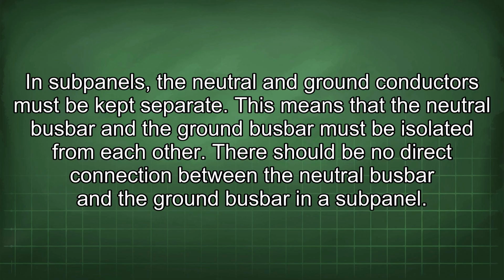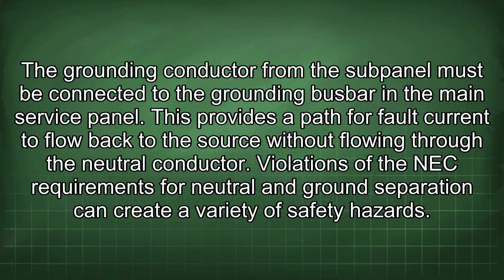In subpanels, the neutral and ground conductors must be kept separate. This means that the neutral busbar and the ground busbar must be isolated from each other. There should be no direct connection between the neutral busbar and the ground busbar in a subpanel. The grounding conductor from the subpanel must be connected to the grounding busbar in the main service panel. This provides a path for fault current to flow back to the source without flowing through the neutral conductor. Violations of the NEC requirements for neutral and ground separation can create a variety of safety hazards.